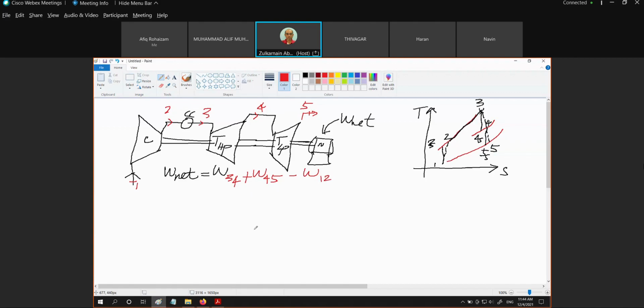And we have another arrangement whereby we use what is called the power turbine. Meaning that we separate this power turbine, which is the low pressure turbine. We use it only to run the electrical generator which produces the W net, while the high pressure turbine is used to run the compressor only. So in this type of schematic diagram, it would look like this.